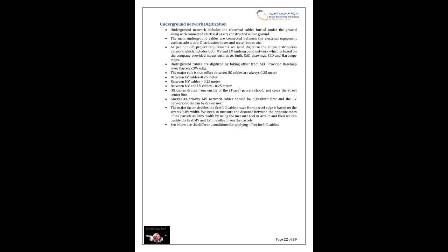Centerline. Always as a priority, MV network cables should be digitalized first, and the LV network cables can be drawn next. The major factor that decides the first UG cable drawn from the parcel edge is the street row width. We need to measure the distance between the opposite sides of the parcels as the row width by using the measure tool in ArcGIS, and then we can decide the first MV and LV line offset from the parcels. See below the different conditions for applying offset for UG cables.